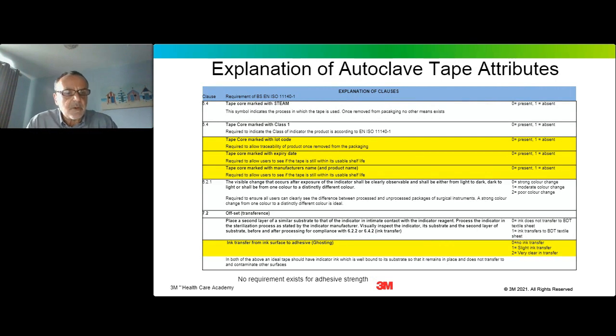Looking at the requirements of standard 11140 Part 1: first, the tape core. As you know, the autoclave tape is wrapped around a central core, usually made of cardboard, and the word 'steam' should be marked on the inside of the core to clearly indicate this is autoclave tape and not tape for another process.